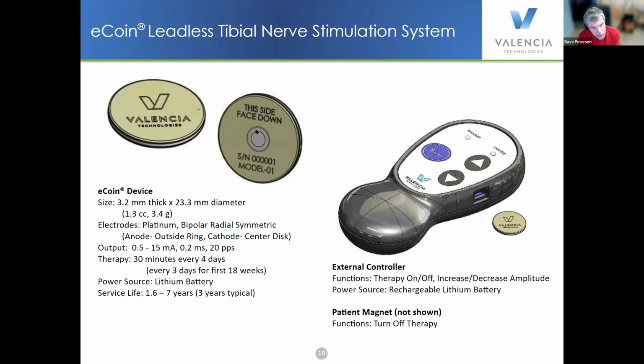You could program this stuff and play with it, but there really isn't a lot of value. The only thing that really gets adjusted in this device is you turn it on and you adjust the amplitude. So as far as how you set it up from a clinical perspective, it's pretty simple. It uses a lithium battery, and the service life can range from 1.5 or so to 7 years, but you're typically looking at a 3-year service life with a device like this before it has to be replaced. The external controller is kind of interesting.